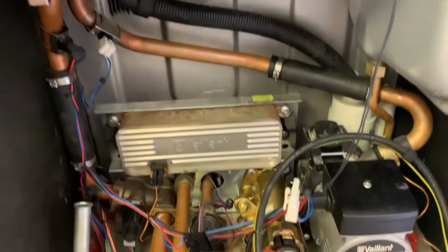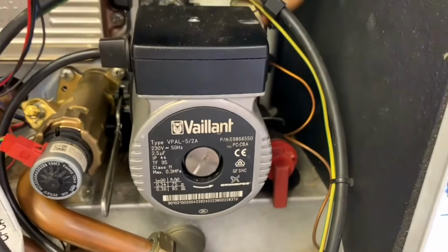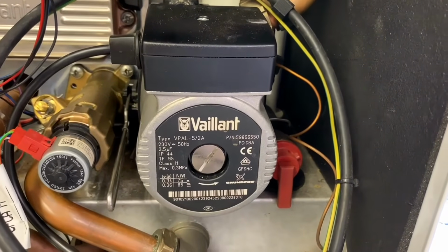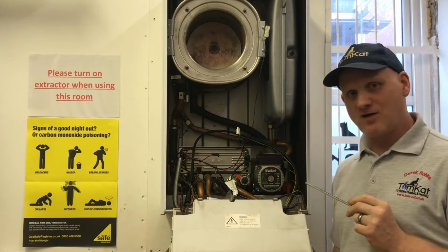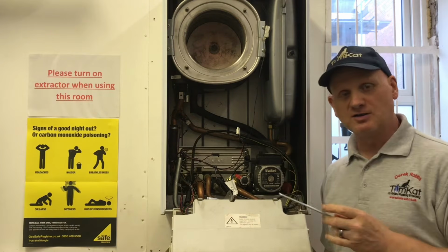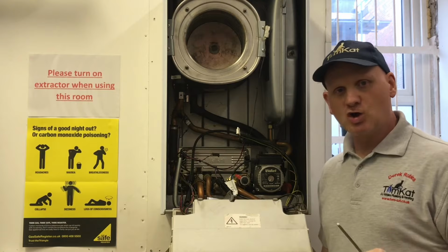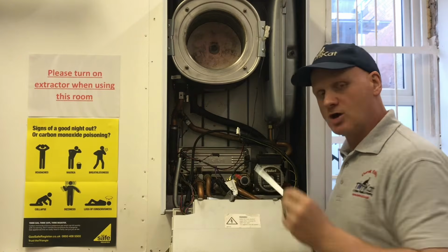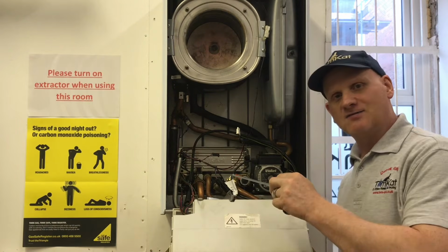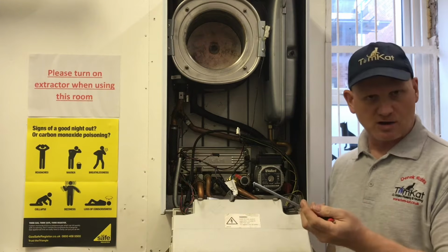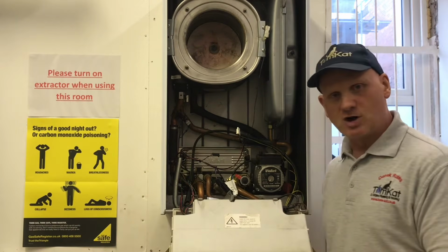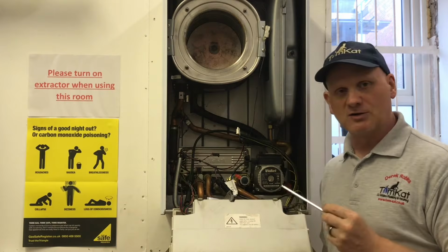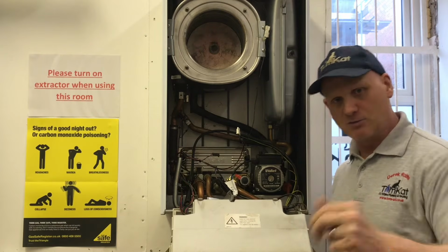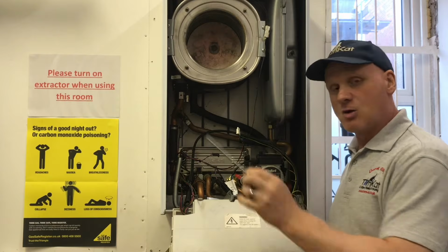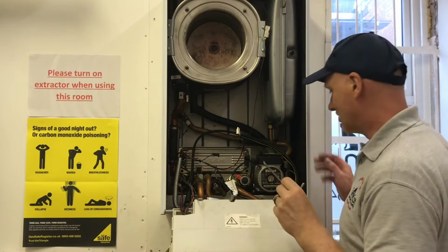So let's actually get stuck in and start taking things apart like we do normally inside a boiler casing, and let's get this pump off. Now to remove this pump is pretty straightforward. We're just going to take the head off first. But remember, before you do any work whatsoever on the wet side, the water side, you would need to isolate the valves underneath on the flow and return or the cold water coming in, drain the water through the taps and then drain the boiler itself through the drain. So we'll have a look at that when we look underneath later. So there's no water in this boiler, so this is dead easy to strip.